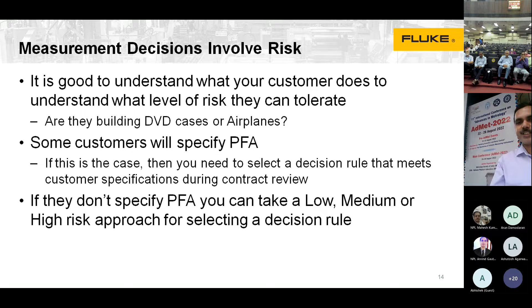Because in 7.1.3, while reviewing the customer's query, if the customer asks for a statement of conformity, it needs to be finalized during that contract review and agreed with the customer. If it is inherent in the standard, then the risk is covered in that standard. But if it is according to a specification, and the customer specifies the specification limit, then the cases of false accept and false reject need to be agreed during the contract review, before the commencement of the calibration or testing. If they don't specify a PFA, you can take a low, medium or high risk approach for selecting a decision rule. In such cases, the laboratory needs to carry out the risk analysis in detail, in elaborate form.